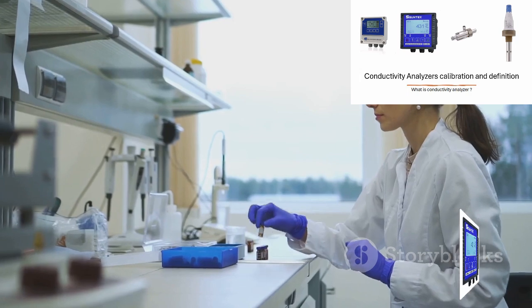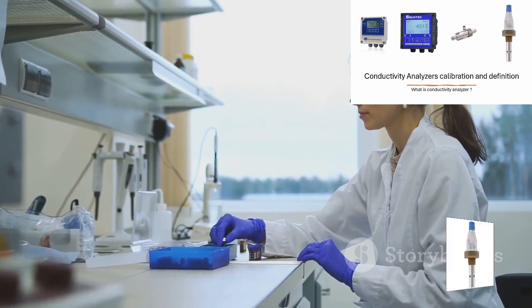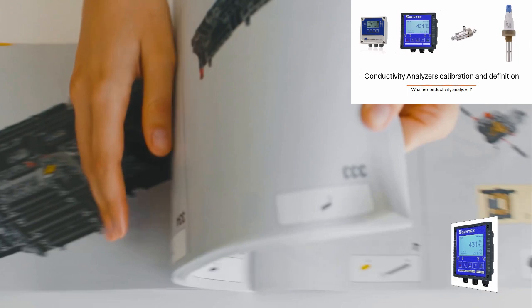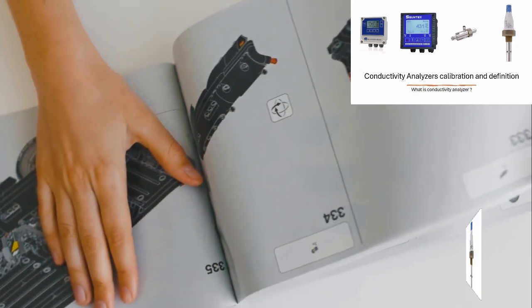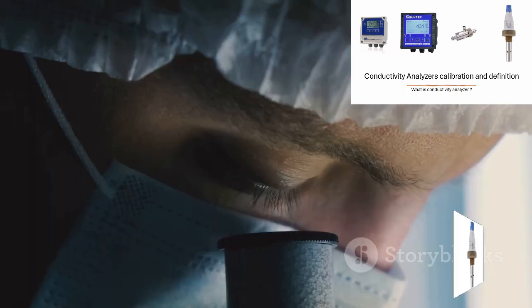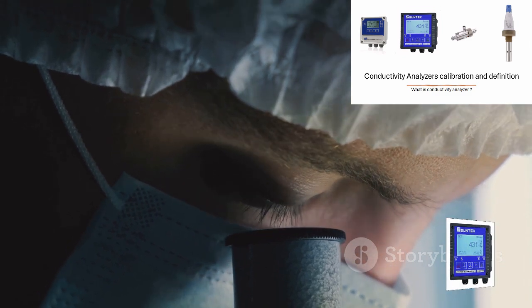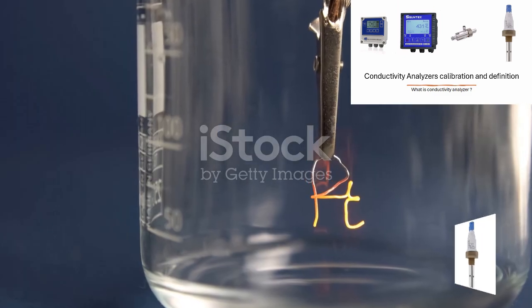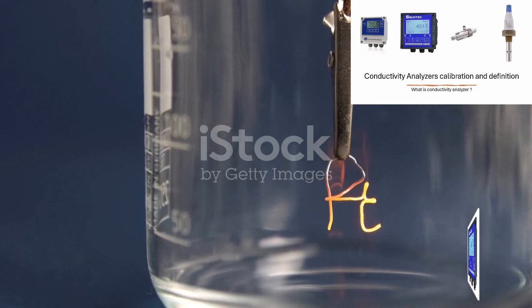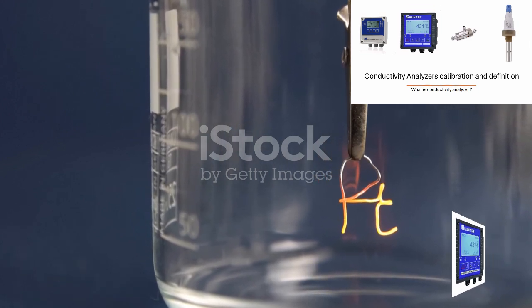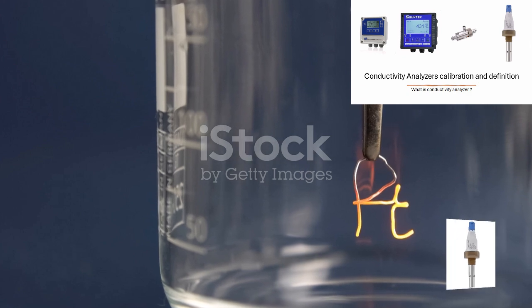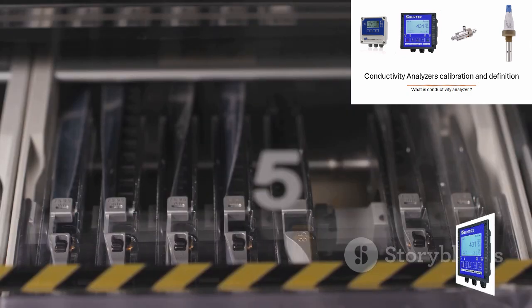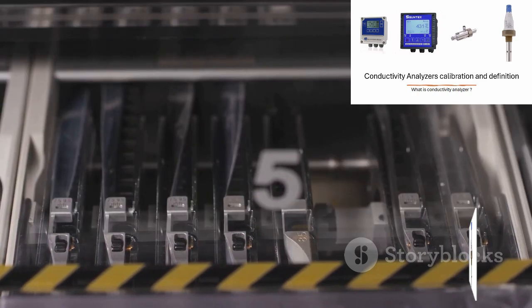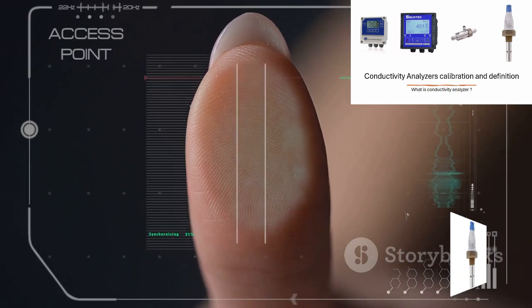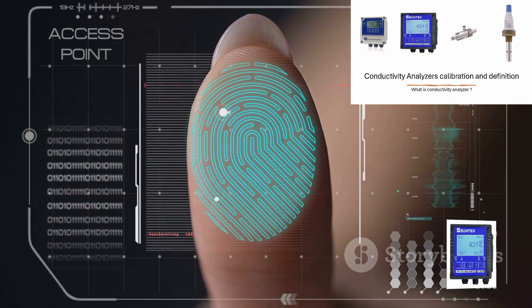After rinsing, some sensors should be stored dry, while others need to be kept moist. Always check your sensor's instruction manual to see what it recommends for happy, long-term storage. Proper handling is just as important as proper storage. The electrodes on a conductivity sensor are delicate and often coated with special materials like platinum black to increase their surface area and accuracy. That's why you should never touch them with your fingers or scrub them with a brush. The oils from your skin or the abrasion from a brush can damage this coating, leading to inaccurate readings.